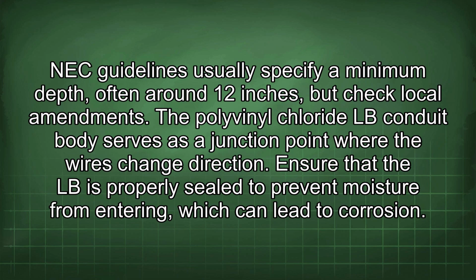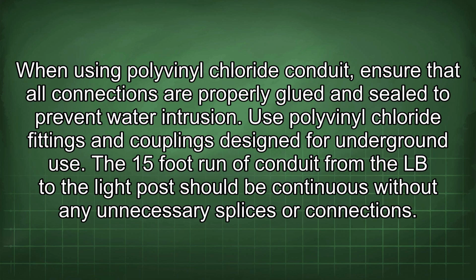The polyvinyl chloride LB conduit body serves as a junction point where the wires change direction. Ensure that the LB is properly sealed to prevent moisture from entering, which can lead to corrosion. When using polyvinyl chloride conduit, ensure that all connections are properly glued and sealed to prevent water intrusion. Use polyvinyl chloride fittings and couplings designed for underground use.